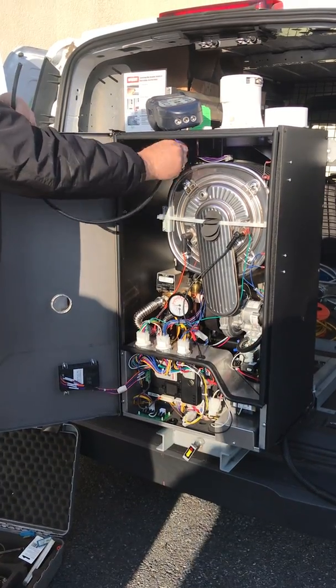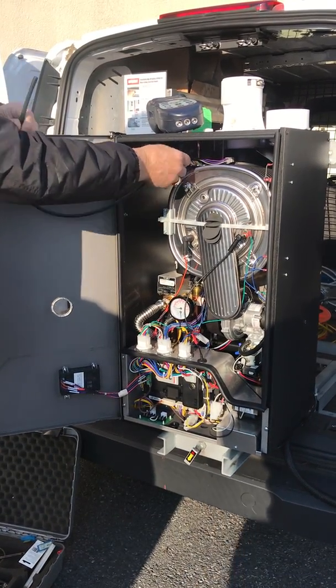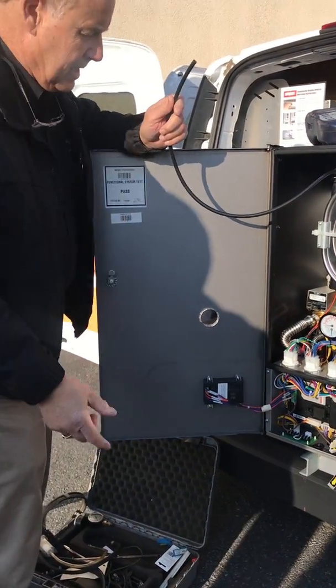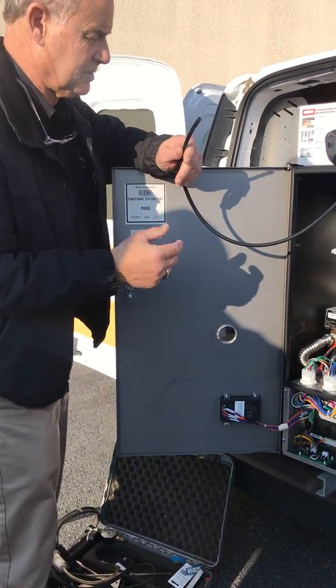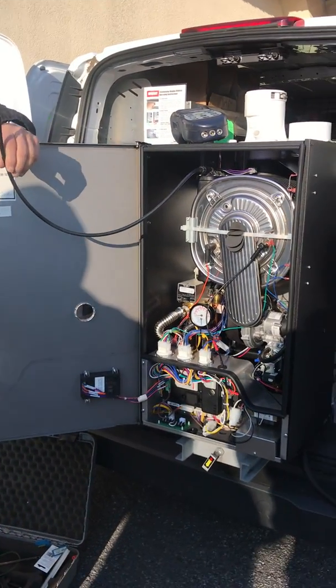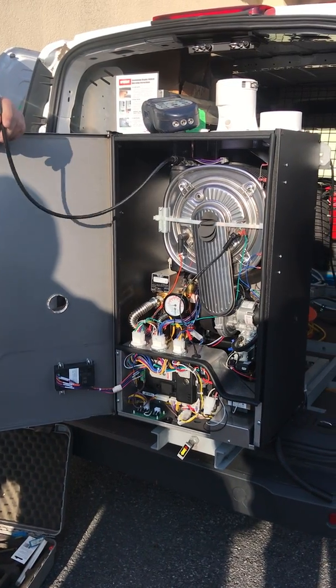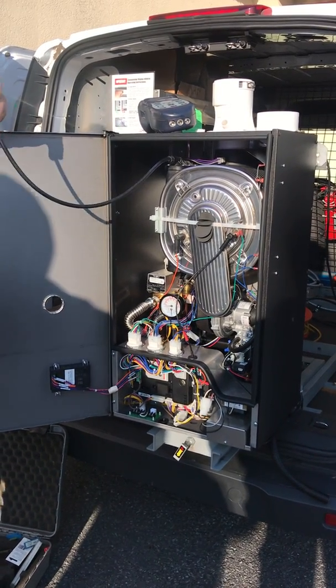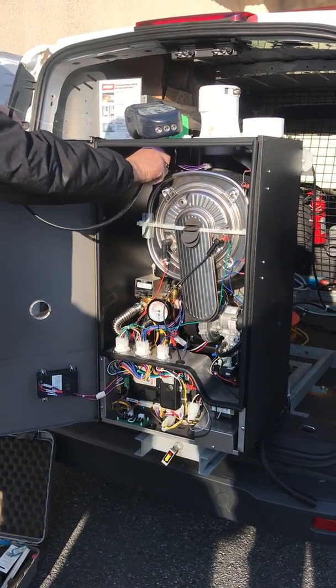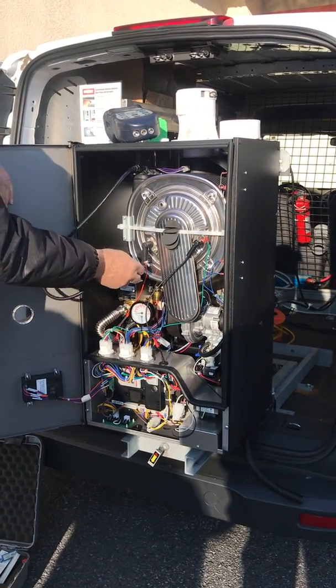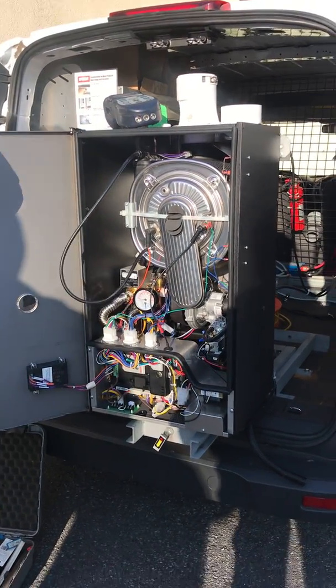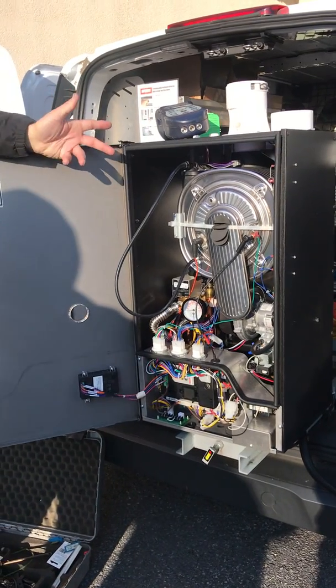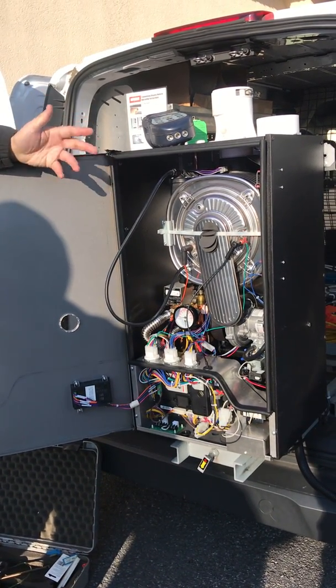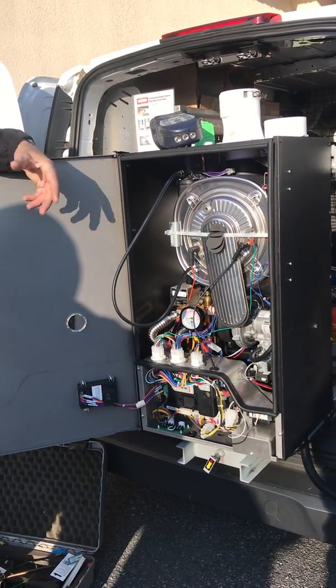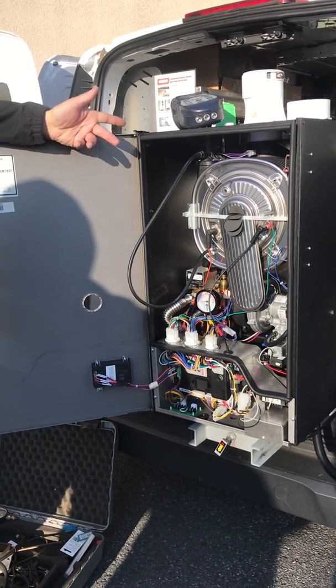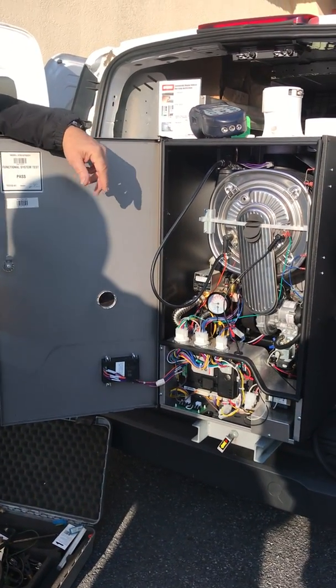So you don't have to put a big pliers on here. I can actually open this up and purge all the air out. If we don't get the air out of this, it's not going to actually kick on your burner. So you got to get the air out of the heat exchanger itself. And I actually saw one guy, I thought it was pretty cool. He actually just stuck it on here. Some guys take it off and they get rid of it. But if I ever have to drain the system and flush it or anything, I want to be able to purge the air. But do not do this.